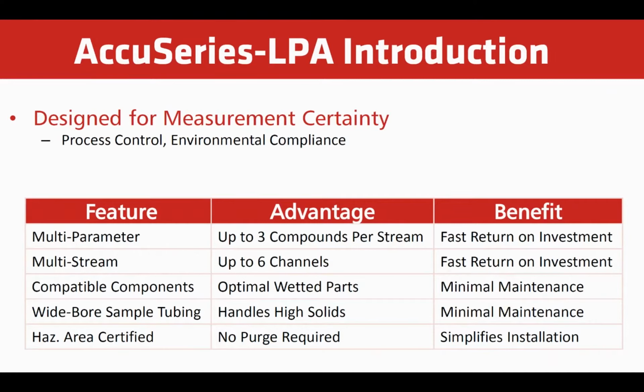Again, you won't have to purchase 6 as long as it's close enough to the different streams. So it's obviously a fast return on investment. We designed these based on the application to have the optimal wetted parts so that it is compatible with your sample stream, so it will, in effect, create minimal maintenance. We use what we call wide bore sample tubing, which is up to a 1/4 inch diameter, so we can handle high solids. And again, we'll create fewer clogs, so minimal maintenance. Less maintenance has to be performed on the analyzer.